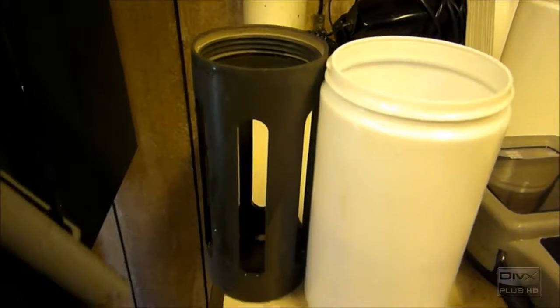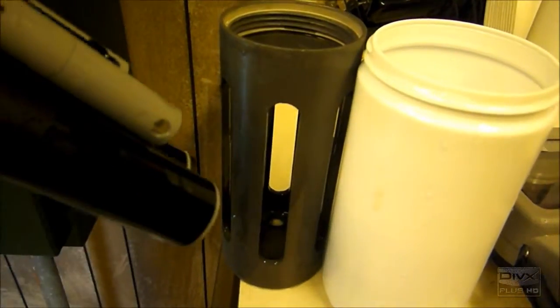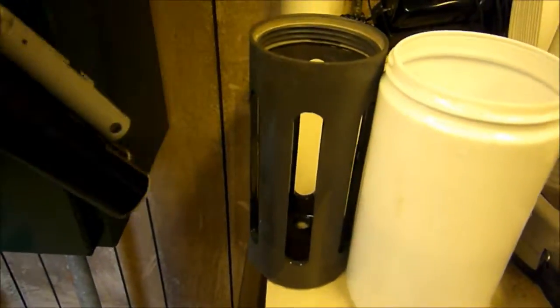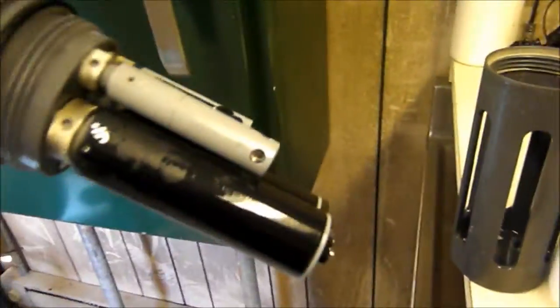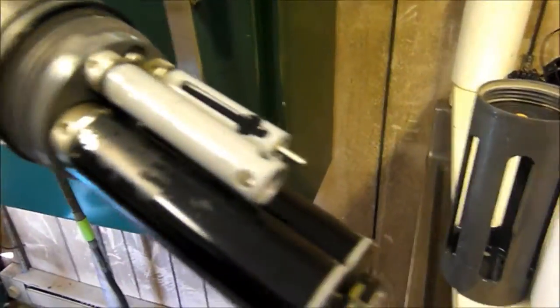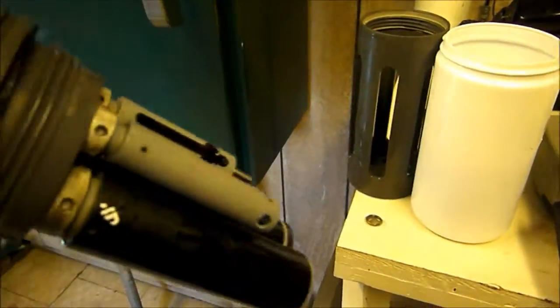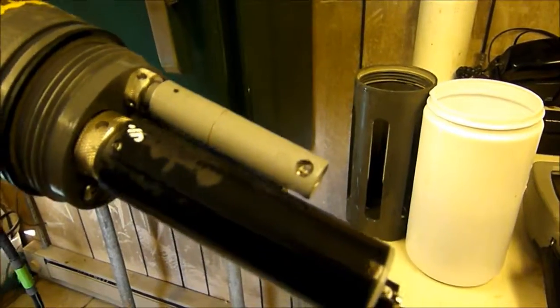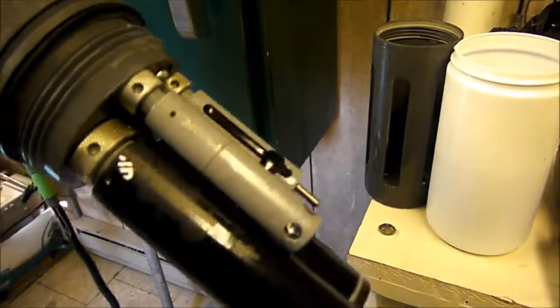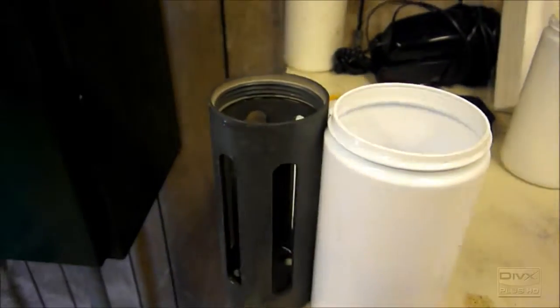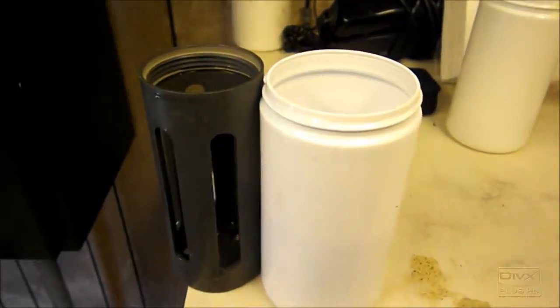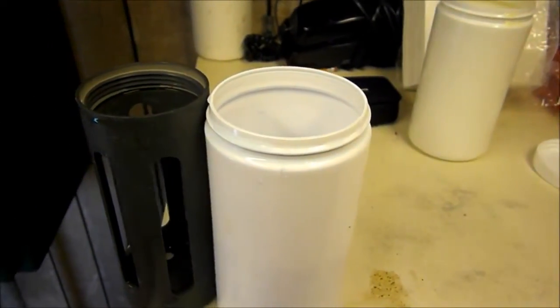You'll want to make sure all calibrations are done using this guard right here. Out of all the different probes, I found that pH lasts the shortest. I'd recommend changing it at least every year, or when it starts to get really slow. And with that, we have successfully calibrated our pH meter. If you have any questions, please let me know.